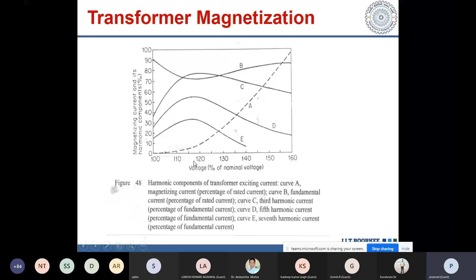And this particular situation normally comes during morning time when most of the industrial loads are off. Then the voltage at the user end, the distribution end, is quite high, and because of that the transformer draws extra magnetizing current. Curve B, which is having a dominant fundamental, is the fundamental current. Curve C is the third harmonic component. You can see here, when the percentage is around 120%, the third harmonic component is quite large. Fifth harmonic is there, seventh harmonic is there. So all these harmonic currents increase when the voltage is around 120%. And this situation normally comes during morning time.